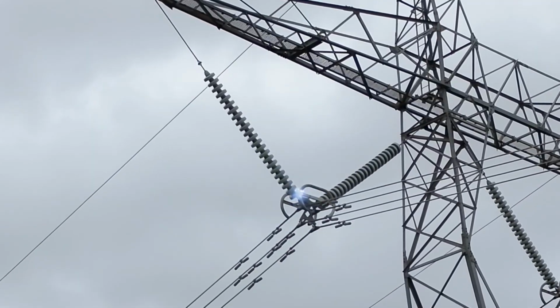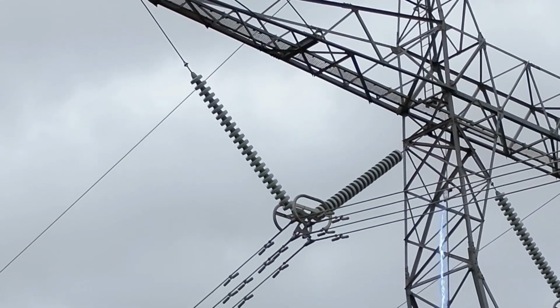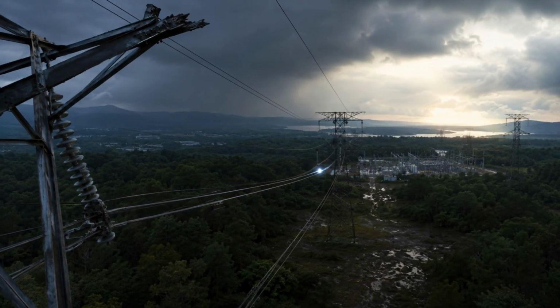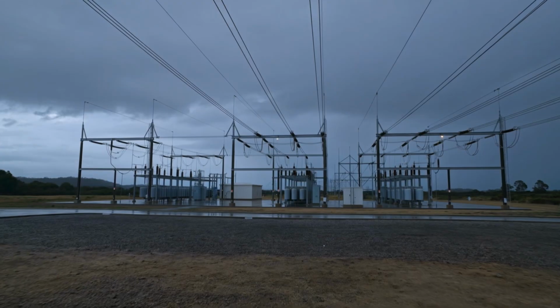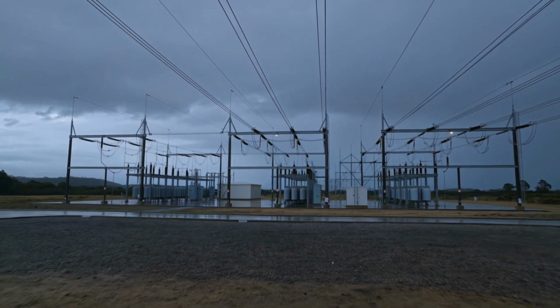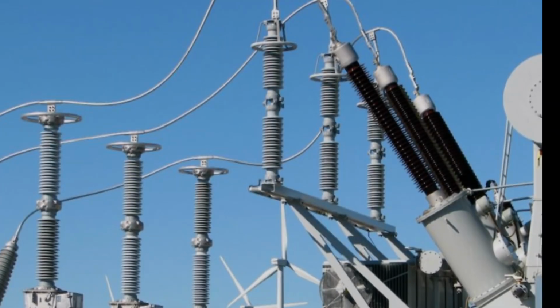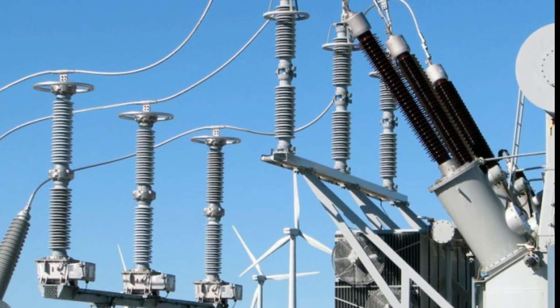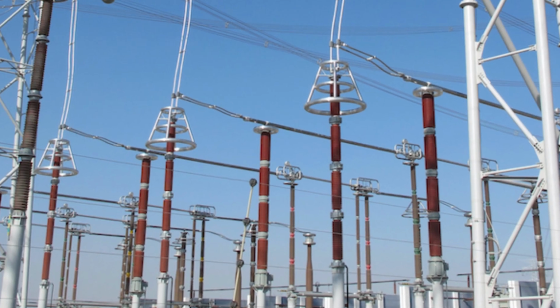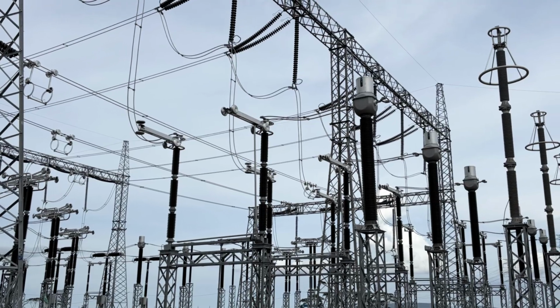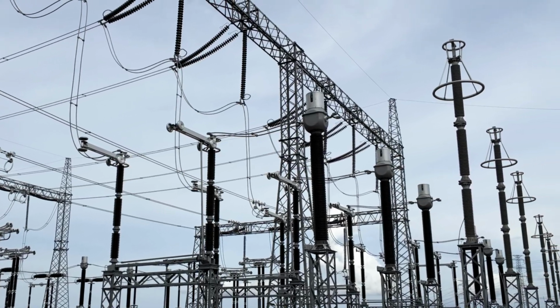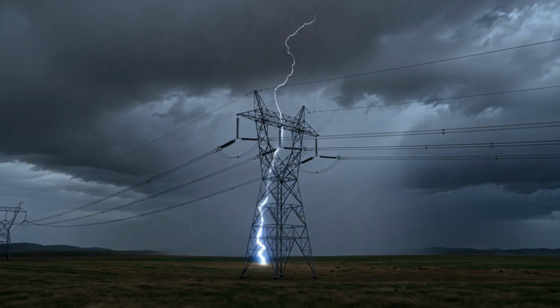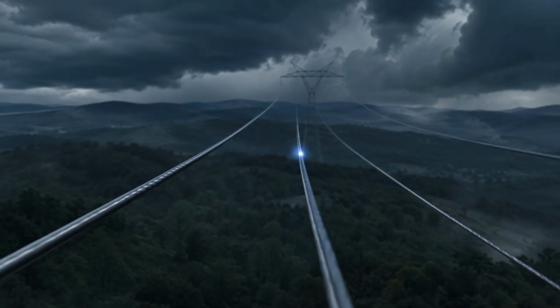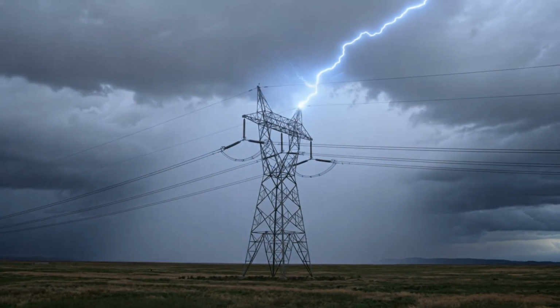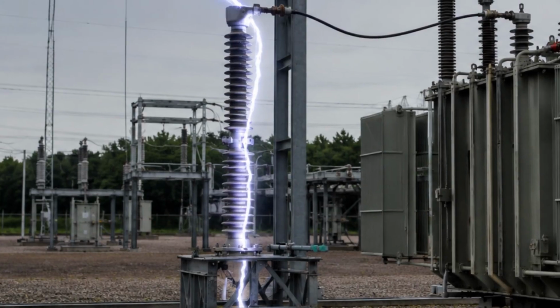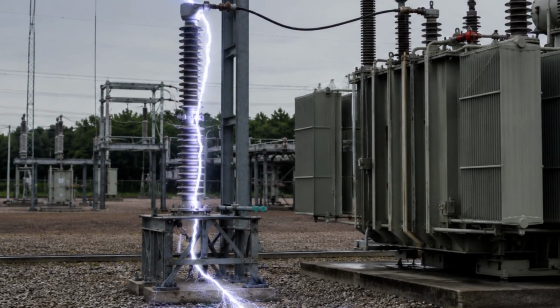Now, a powerful surge can race along the line, and electricity can flow where it should not. Near transformers and substations, special devices called surge arresters give that sudden burst of electricity a safer path into the ground. They usually do almost nothing, but when a dangerous surge arrives, they react almost instantly. They cannot stop the lightning. They try to steer it away from vulnerable equipment.